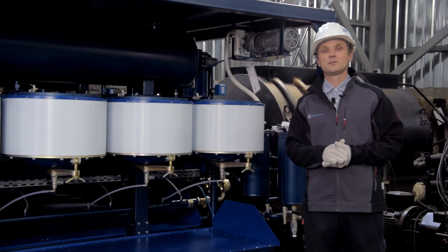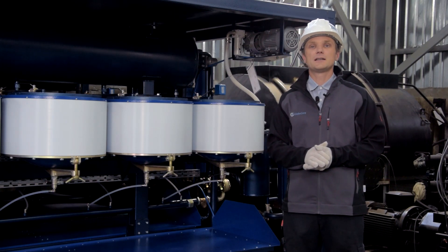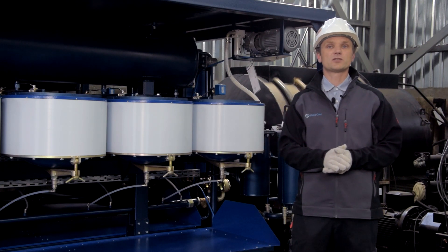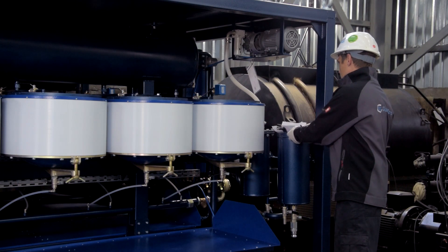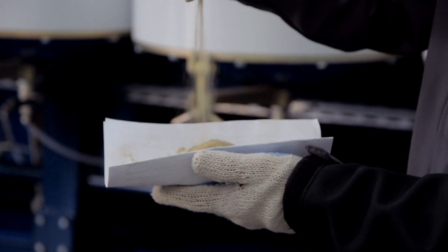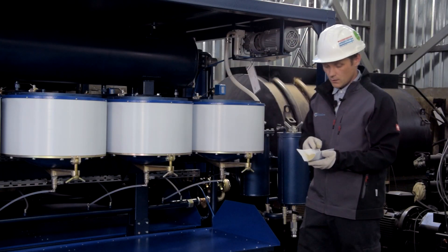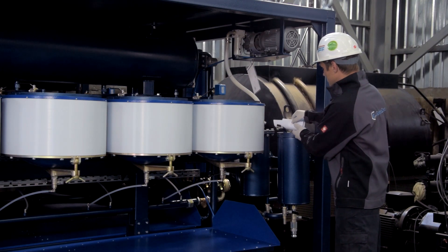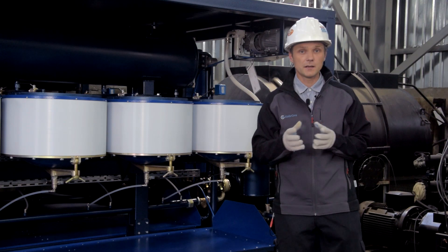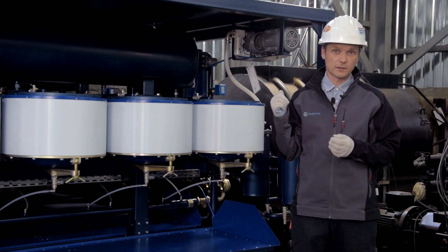Today we'll talk about the UVR unit, the machine which was initially designed to regenerate transformer oil due to chemical interaction with the sorbent — a sorbent called palygorskite, which is actually a kind of whitening clay. The key is to bring into contact the oil, transformer oil, and the sorbent palygorskite.